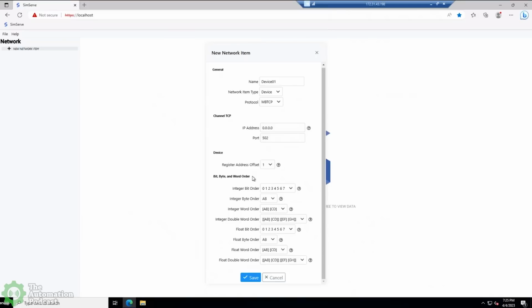some CPUs and some PLCs like to store integers with bits going from left to right. Others like to go right to left. And then when you try to make the two talk to each other over Modbus, you'll see number 1, 2, 3 in one device, but when it gets read into another device, it looks completely different. That's typically because the bit, byte, or word order is off.